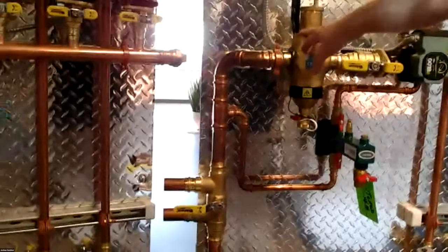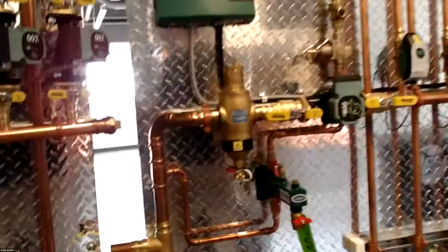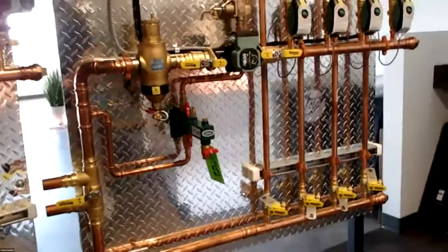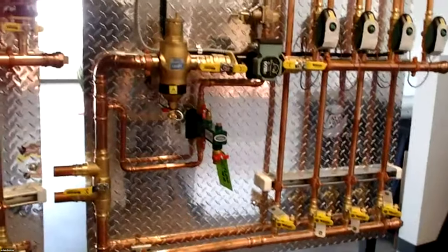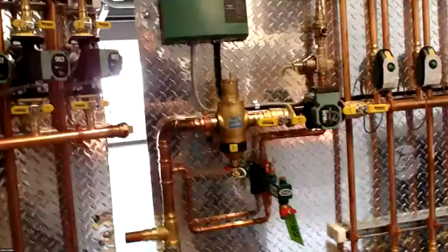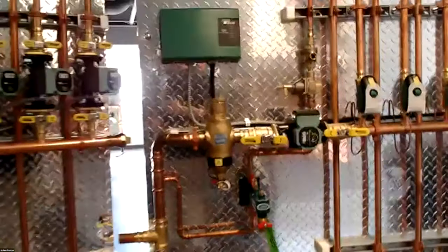One thing to note with closely spaced T's: I've seen delta T issues where you have the closely spaced T's and the hydraulic separation or the air separation is like 10 feet away. I've seen air issues with that where we pocket air and we can have delta T problems. So make sure that air separation is within 5 feet of those closely spaced T's to avoid the problem.